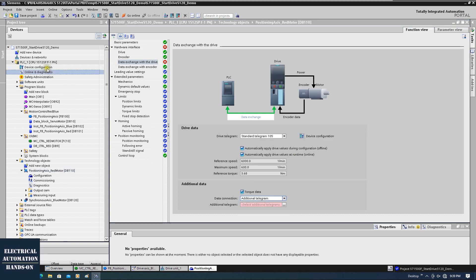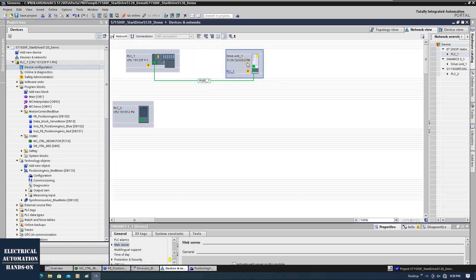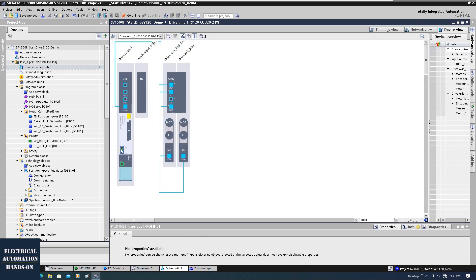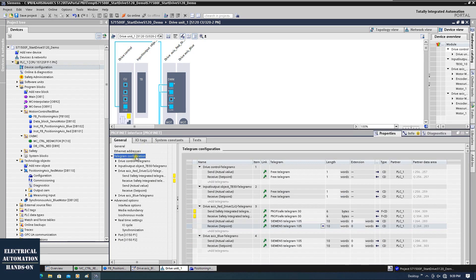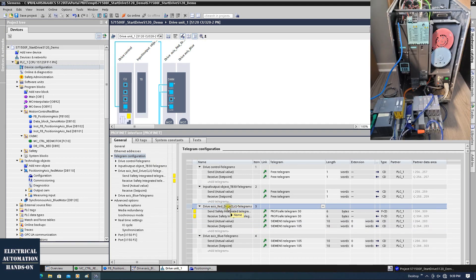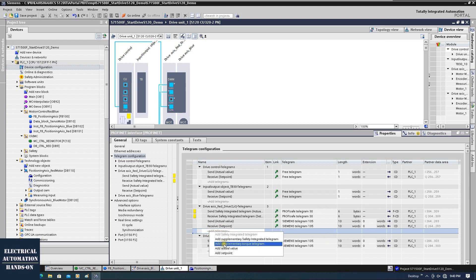First, we need to go to the hardware configuration and go to the drive. Let's click on this CU. From this telegram configuration, for my motor servo drive, as shown in the previous videos, I showed how to enable STO and SS1 — that's why there is telegram 30. For normal servo control we use telegram 105. To enable torque limitation, we need to double-click and click 'Add supplementary torque telegram'.